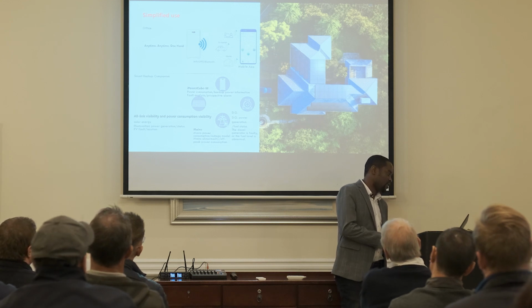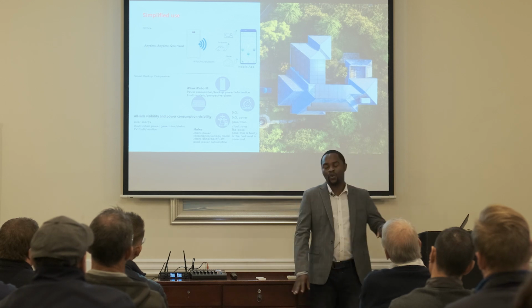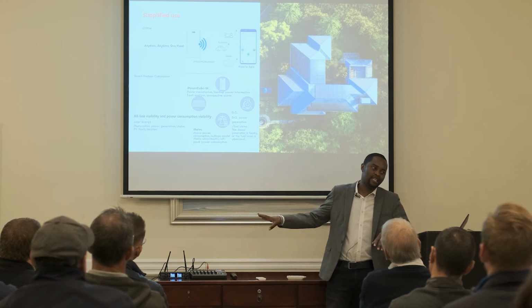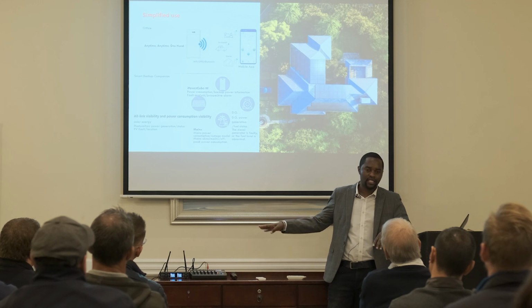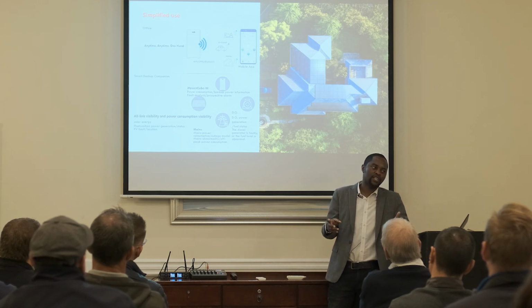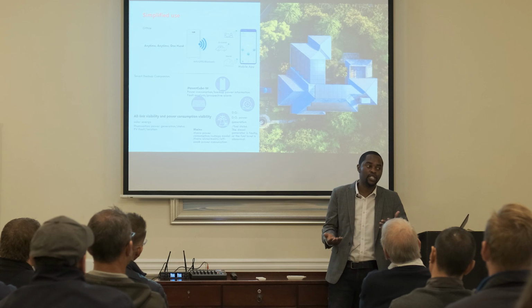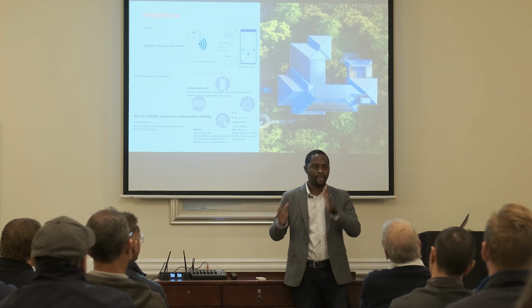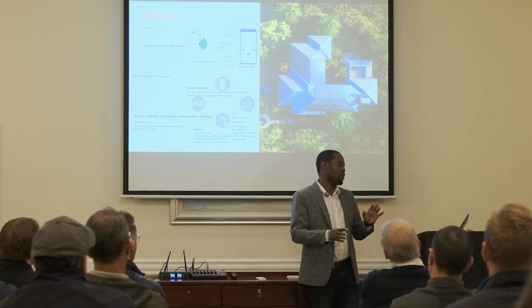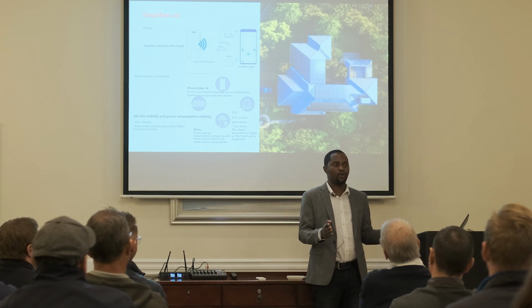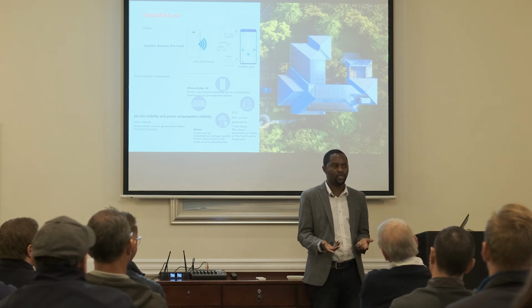Then you can check on this now, there's the genset integration. Ralph, my colleague, has also typed about it. So we actually don't have a genset port. We don't have a generator port on the inverter, so the integration is a semi-integration. It's not a full integration where you have a gen port and wire your generator to the inverter. But when you are wiring your generator, you need to wire it on the grid port via a changeover switch.